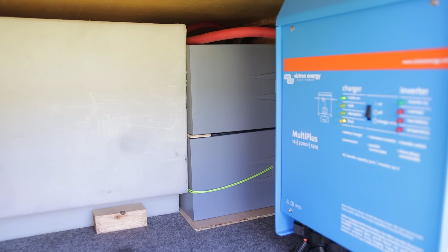But we're bumping up against the limitation of what this inverter can draw, and we wanted to eliminate that restriction. Volts times amps gives us our wattage, so looking at this inverter, it's 3000 VA - divide that by the voltage and it shows we can draw 250 amps with this inverter, not to mention if anything else is on.